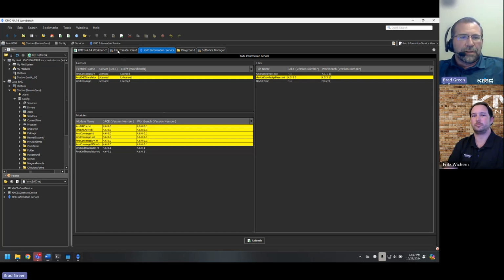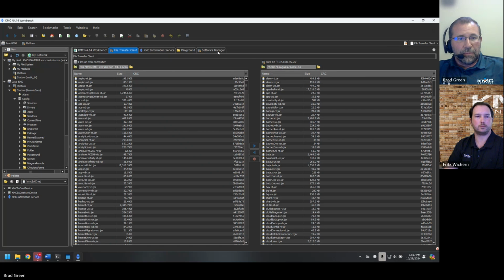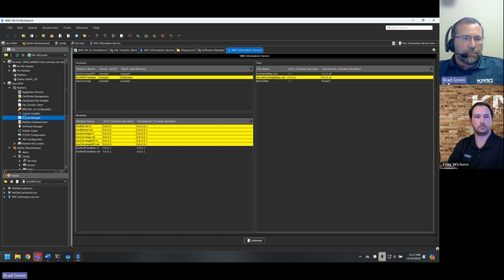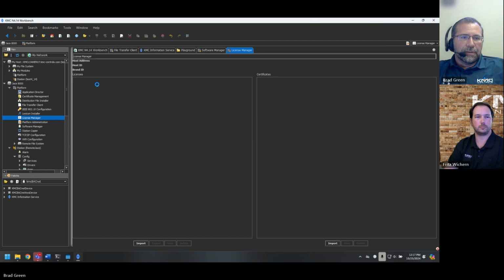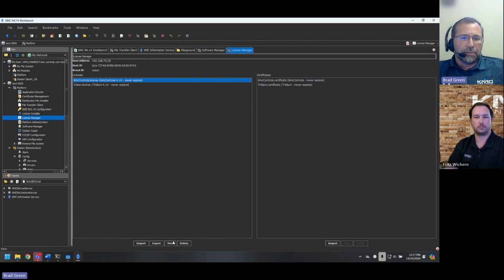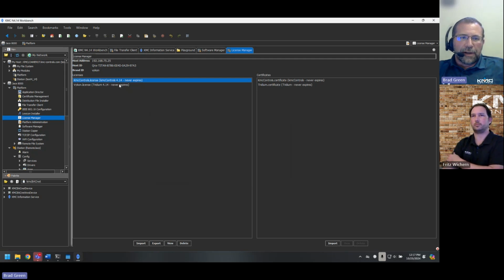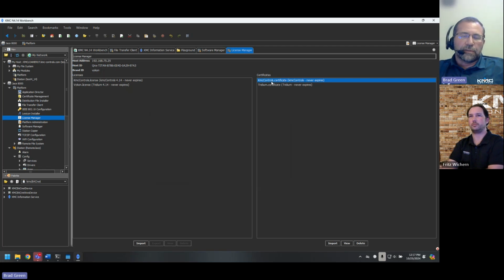So, first thing that I want to reiterate is where Fritz was talking about to find your license. You probably already know, but License Manager. You're going to view your license for the KMC controls license here, and click view. You're going to be looking for that KMC Converge feature when you're wanting to license Converge there. And in order for it to operate properly, you do need the KMC control certificate. So sometimes that gets missed, especially if you do it manually by adding that license in. So if you're having an issue, you might want to check that certificate as well.